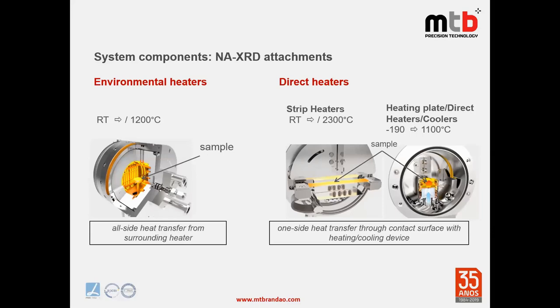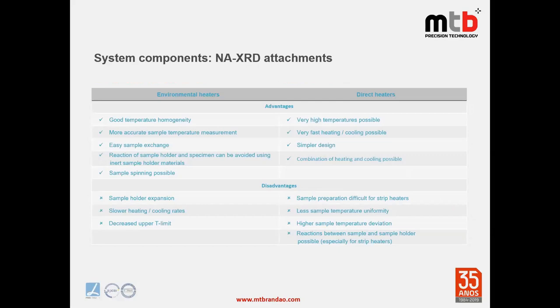There are two types of heaters: environment heaters and direct heaters. Environment heaters offer good temperature homogeneity, more accurate sample temperature, easy sample exchange, and sample spinning; while direct heaters allow very high temperatures, very fast heating and cooling, and a simpler design. Disadvantages of environment heaters include slower heating/cooling rates and upper temperature limits; disadvantages of direct heaters include less temperature uniformity and possible reaction between sample and heater wall.